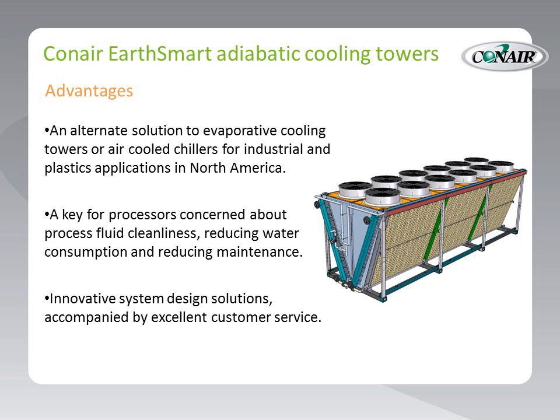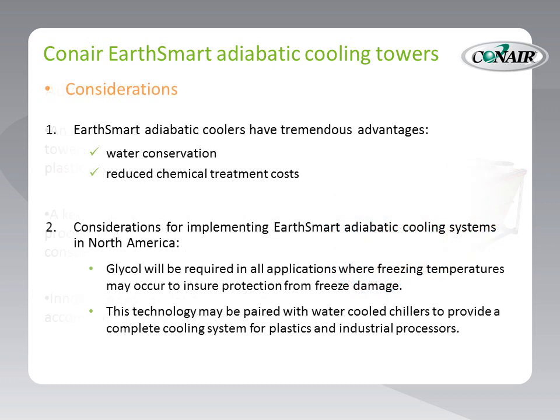The Conair heat transfer team has a goal and a promise to provide an alternative to evaporative cooling towers for applications that require cleaner process fluids and minimal water consumption. While adiabatic cooling has significant water consumption advantages, not every application can take advantage of this technology. For instance, Conair will provide glycol in areas that may be subject to below-freezing temperatures. And in most cases, Conair will pair this adiabatic technology with additional system components to provide customers with a complete solution.